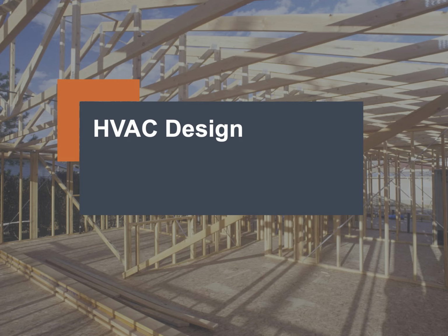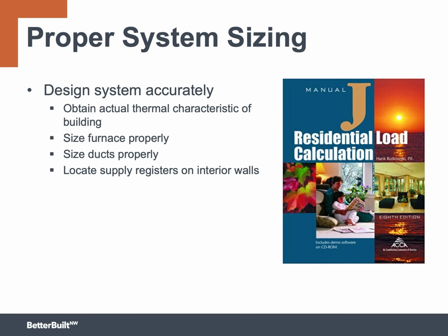Ducts are not often designed in residential buildings. Instead, duct length and diameter are chosen by experience, intuition, and rule of thumb. It isn't necessarily a bad approach for conventional homes. Most heating contractors have learned over the years what size of ducts they need, and the system works pretty well. But now we really need to go back to the design step because we've changed the conditions quite a lot. Heating contractors need to develop new intuition about how houses are going to work now that the ducts are inside conditioned space. It makes sense to go back to this design step and do the full duct design to at least inform this new level of intuition. Many HVAC contractors get used to sizing systems for homes built to basic code, and often those systems look very much alike.